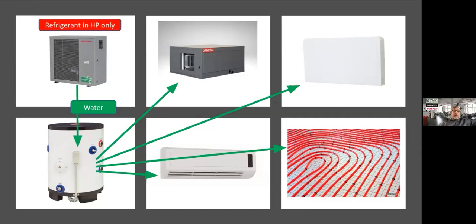From that buffer tank out to all the different emitters, it could be an air handler, like the middle picture in the top, which would be taking warm fluid or cold fluid, turning it into an emitter right behind the fan coil there. We blow air over it, and then we blow that conditioned energy across the building. Upper right-hand corner is a wall-mounted unit. Lower right-hand corner, standard PEX in a floor slab, and then the middle picture in the bottom is just the standard head that we'd use on a ducted mini split. All of those can do some form of heating and cooling. The slab can also be used for cooling. It's just a bit trickier.